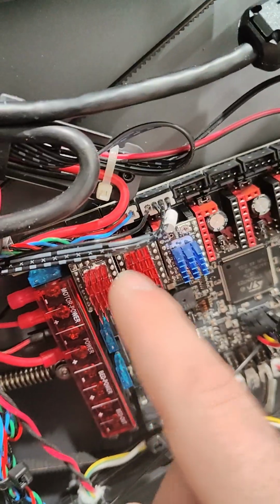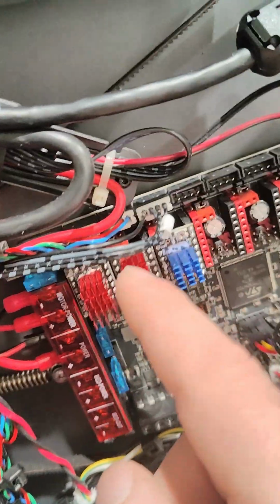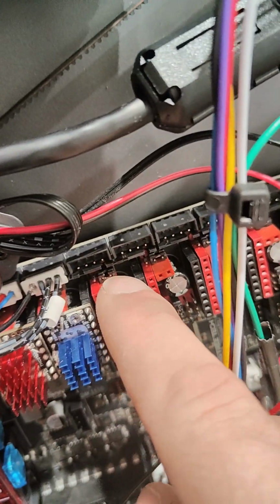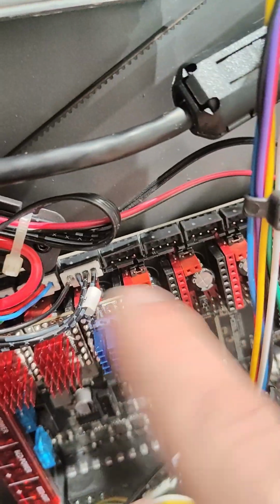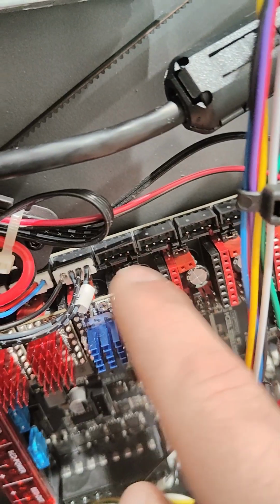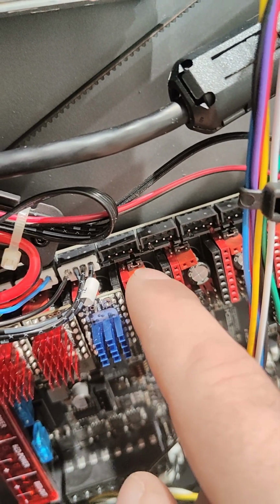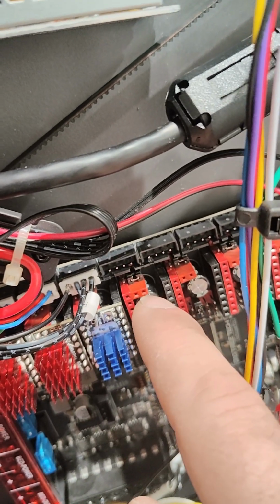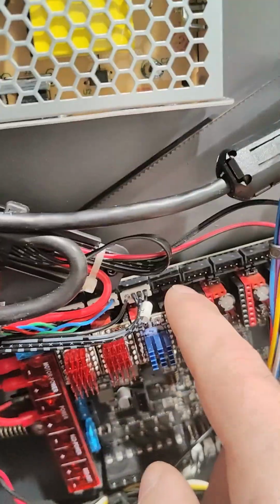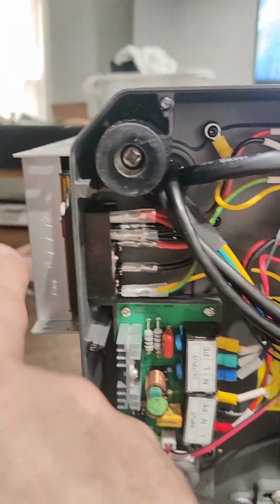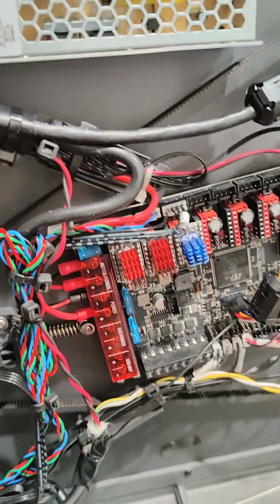And if you're going to put these in 48 volts or higher, there's a jumper. See that jumper for these two? On top of those they'll have the same jumper, and it should be in that slot instead of the slot that it's currently in. The slot it's currently in is for 24 volts off this power supply. If you switch it to the other pin, it goes to this power supply, which is the 48 volts.